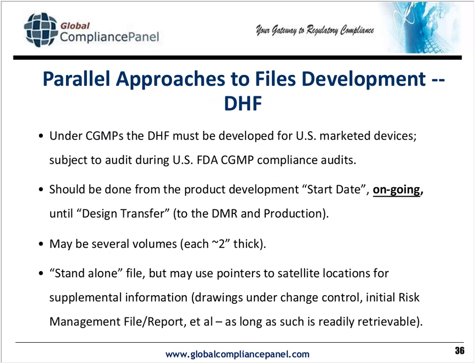Again, development of the design history file, as I mentioned at the very beginning, I would recommend that you do it ongoing, as I've emboldened here, that you don't try to do it after the fact. Get the tabs formulated, get the binders, or if you're doing it electronically, get the file set up, and then add to it as you go along.